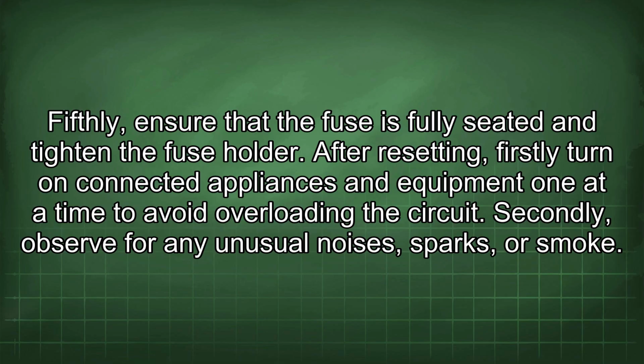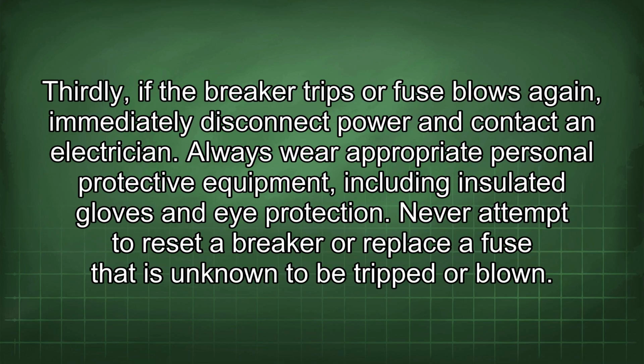After resetting, firstly turn on connected appliances and equipment one at a time to avoid overloading the circuit. Secondly, observe for any unusual noises, sparks, or smoke. Thirdly, if the breaker trips or fuse blows again, immediately disconnect power and contact an electrician. Always wear appropriate personal protective equipment, including insulated gloves and eye protection.